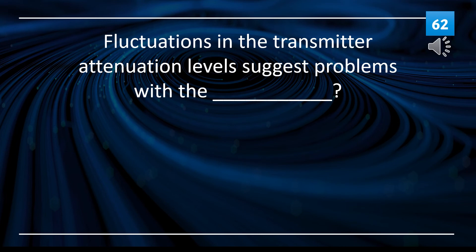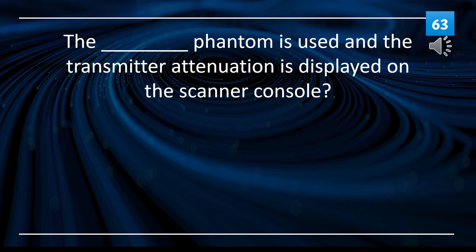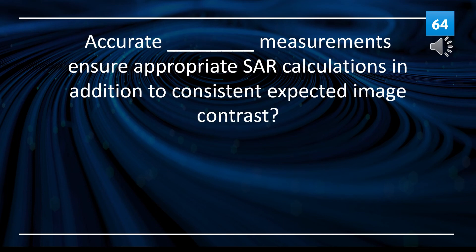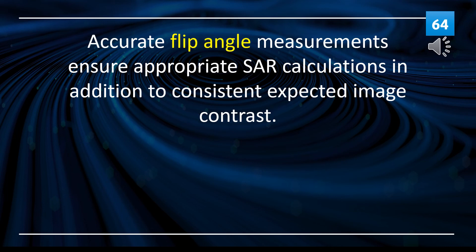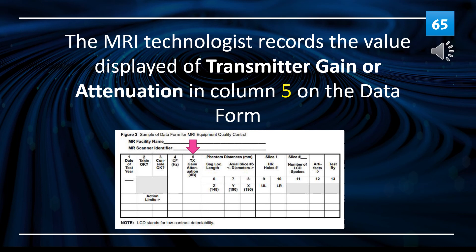Fluctuations in the transmitter attenuation levels suggest problems with the radio frequency chain. The ACR MRI Phantom is used and the transmitter attenuation is displayed on the scanner console. Accurate flip angle measurements ensure appropriate SAR calculations in addition to consistent expected image contrast. The MRI technologist records the value displayed of transmitter gain or attenuation in column 5 on the data form.